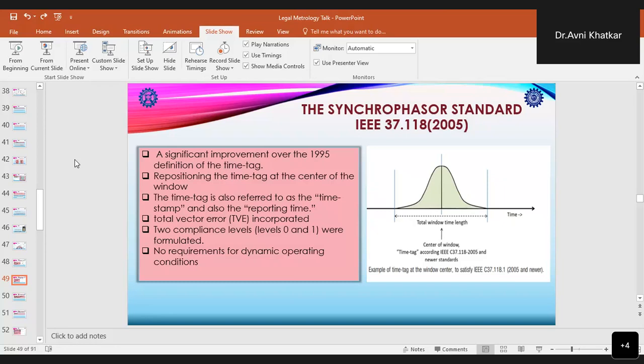In this 2005 standard, along with the center of the window time tag, or the timestamp, also known as the reporting time, the notion of total vector error, that is TVE, was also incorporated in order to evaluate the phasor measurement requirements. Two compliance levels, level 0 and level 1, were formulated to assess measurement accuracy over a range of magnitudes, frequencies, and phase angles. However, the main shortcoming of this standard was that it did not include any requirements for dynamic operating conditions, and hence it could only be applied to steady state conditions.